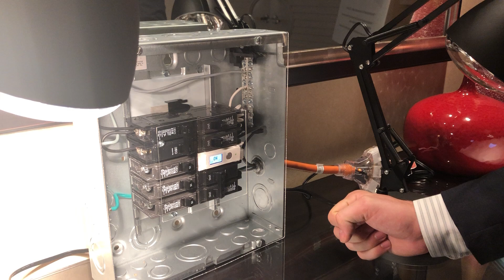With that complete solid state nature, we're able to bring down the total amperage. This circuit breaker is set to trip at 26 amps, but we actually brought that down to 3 amps.